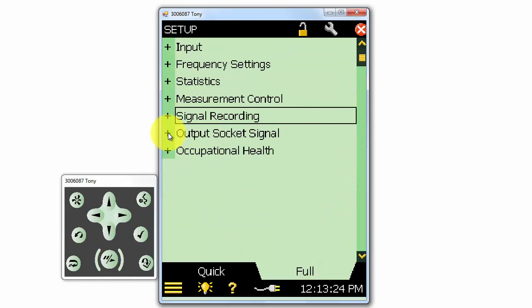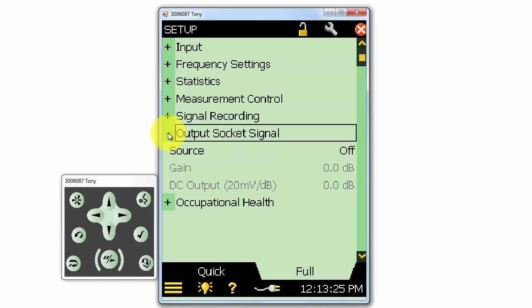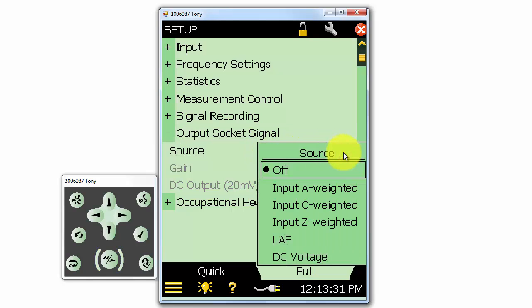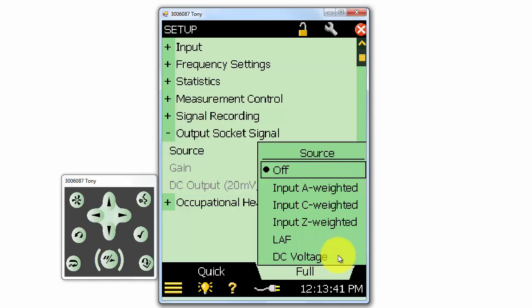Under output socket signal, we can select what comes out of the rear output connection on the meter. We can output a direct or frequency weighted signal from the microphone or accelerometer, or a DC voltage that is proportional to the LAF value, or a constant voltage for calibration.